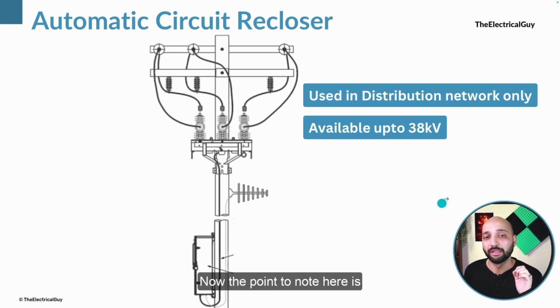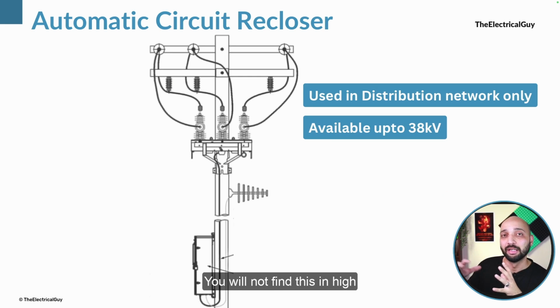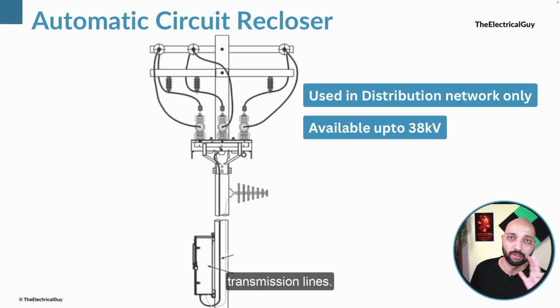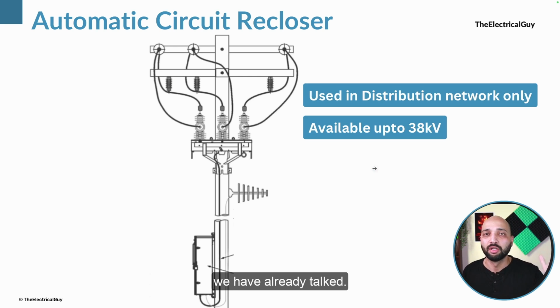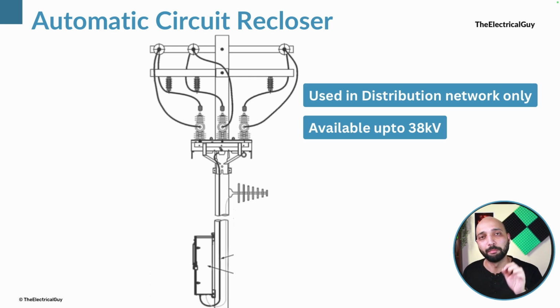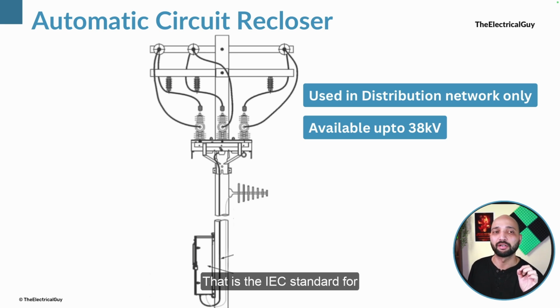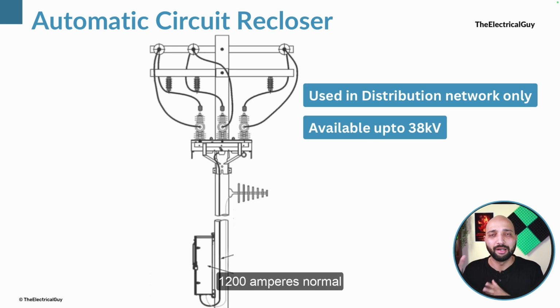Now the point to note here is that they are used only in distribution network. You will not find this in high and extra high voltage transmission lines, and they are available up to 38 kV. The IEC standard for which we have already talked, it's IEC 62271-111. That is the IEC standard for automatic circuit recloser. The current rating depends. It can go from 630 amperes to 1200 amperes, normal rated current.